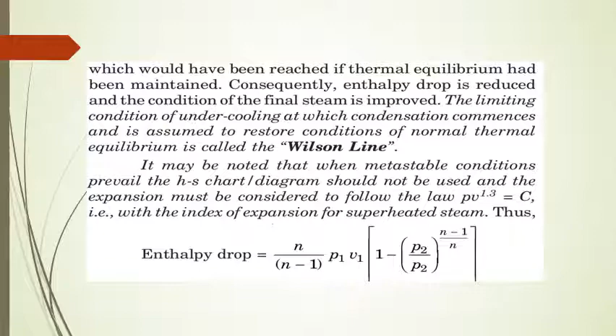It may be noted that when metastable conditions prevail, the HS chart or HS diagram should not be used, and the expansion must be considered to follow the law PV^1.3 = C, that is, with the index of expansion n = 1.3 for superheated steam. Thus, enthalpy drop equals n/(n-1) × P1V1 × [1 - (P2/P1)^((n-1)/n)]. So this formula we need to use.